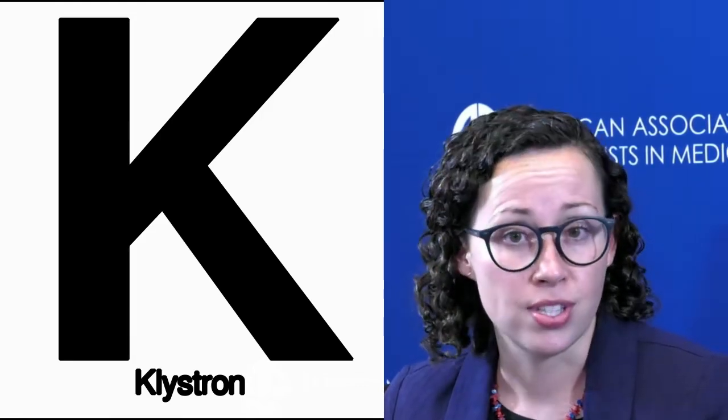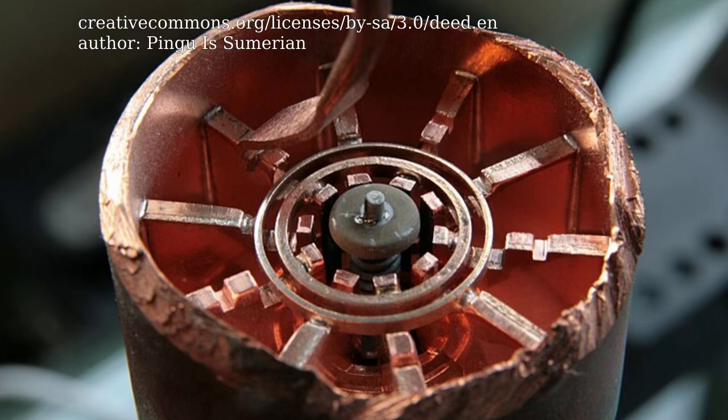A different source of microwave power, a magnetron, is the other type of part that can be used in linear accelerators to generate the power needed to run a linear accelerator.